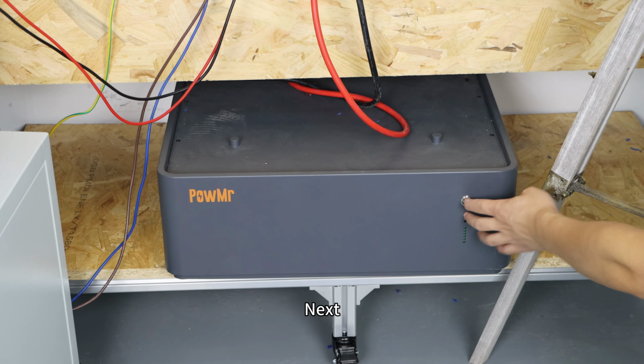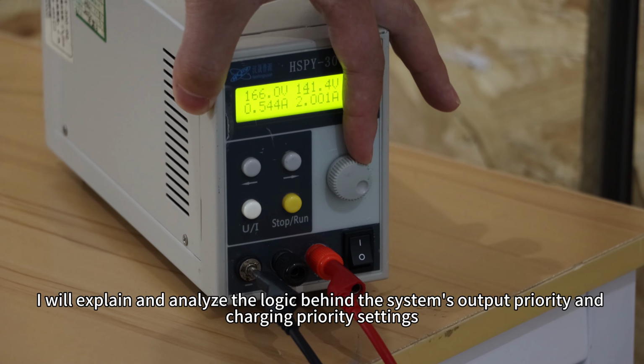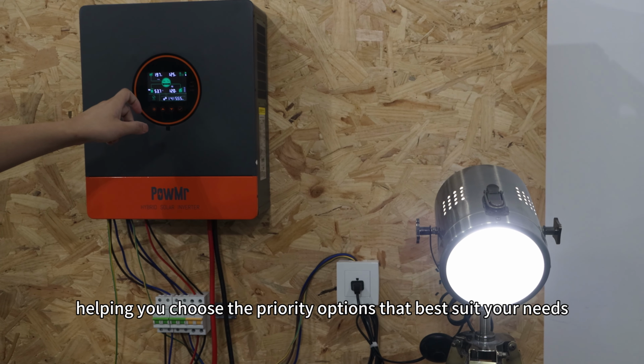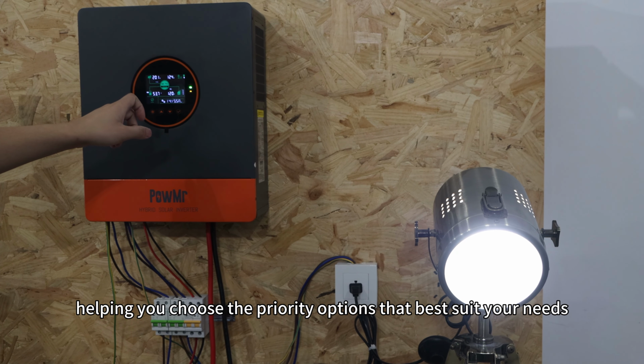Finally, close the AC output circuit breaker, and you can start your loads one by one. If the fault indicator light does not light up, it means your solar system is now operating normally. This concludes the wiring demonstration for configuring the 5 kW system. In the next video, we will explain and analyze the logic behind the system's output priority and the charging priority settings, helping you choose the priority option that best suits your needs.